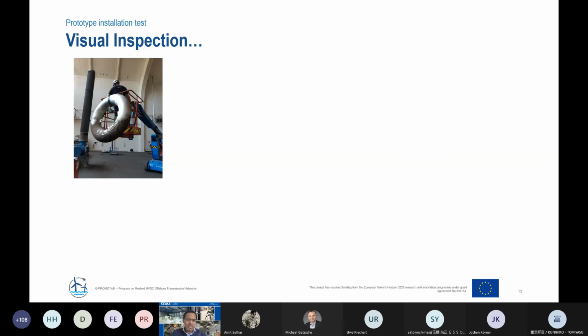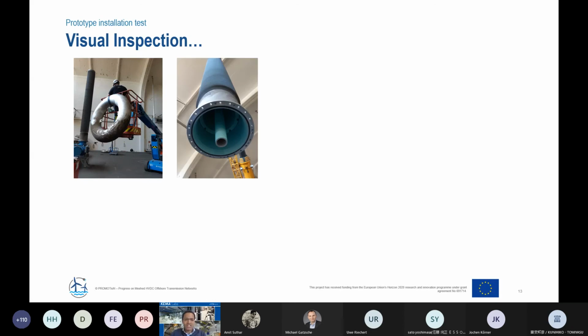We dismantled the unit, followed by a visual inspection, and observed the manufacturer doing the dismantling. Here you see the corona ring taken off the DC bushing. As I said, one of the problems was dust - even though it was cleaned many times, the whole room, it's still there. That's one of the challenges.